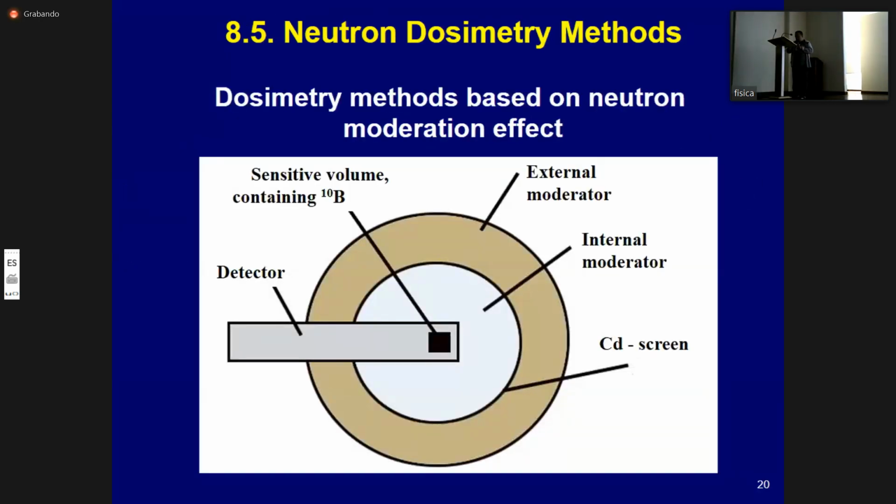And one more mode that we need is to measure dosimetry from neutrons. All currently used neutron dosimeters and radiometers for operational measurements are based on the same physical principle: the registration of the thermal neutron flux density in the central part of the detector. Usually this part is enriched in boron-10, which has a big cross section for the interaction with neutrons, especially thermal neutrons.